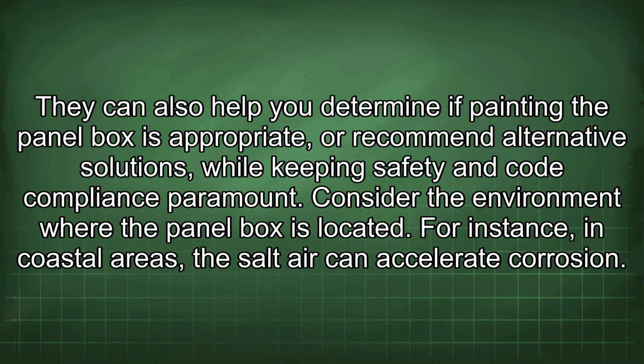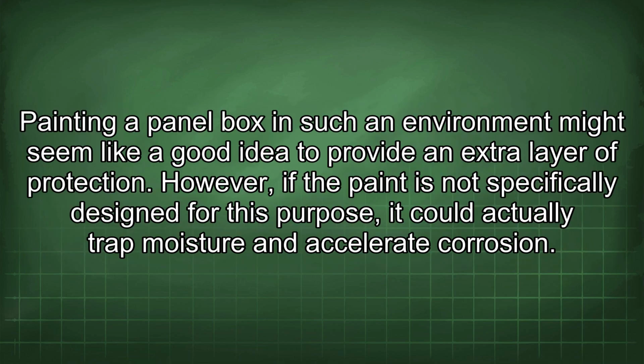Consider the environment where the panel box is located. For instance, in coastal areas, the salt air can accelerate corrosion. Painting a panel box in such an environment might seem like a good idea to provide an extra layer of protection. However, if the paint is not specifically designed for this purpose, it could actually trap moisture and accelerate corrosion.